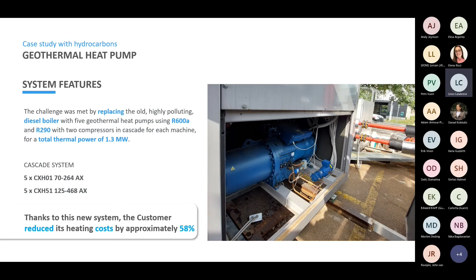They have shared with us the coefficient of performance trends across the full temperature range, from 35 degrees outlet water temperature up to 80 degrees. Overall, the efficiency result is remarkable because when the water is provided at 80 degrees, with a ground temperature of 15 degrees, the overall COP is 3.4.